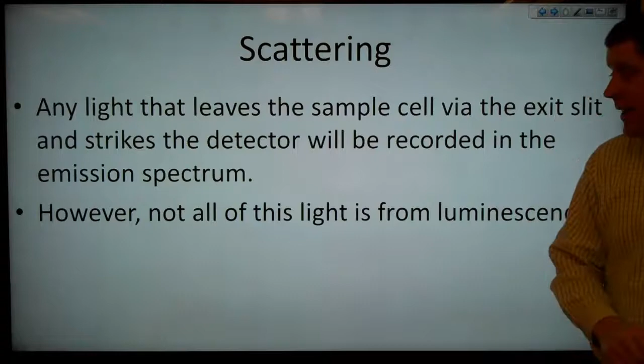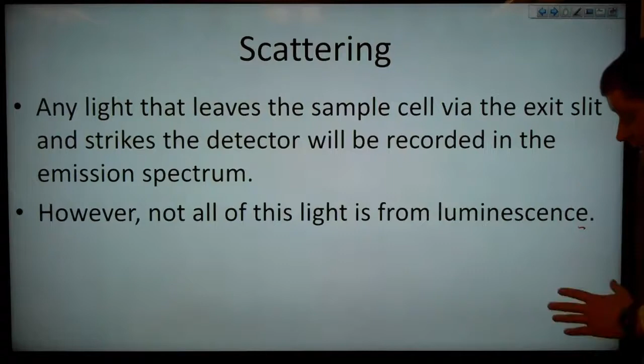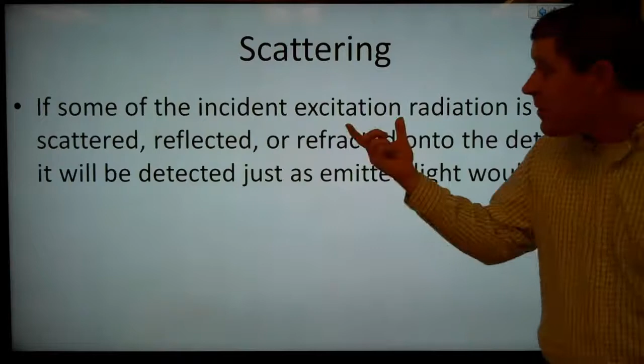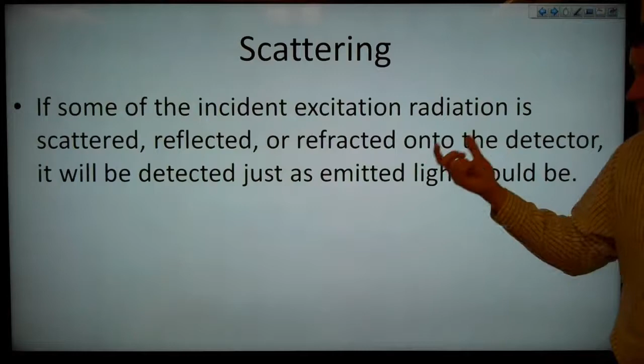So now let's talk about scattering. Any light that leaves the sample cell via the exit slit and strikes the detector will be recorded in the emission spectrum. But not all of this light is necessarily from luminescence, so it's not necessarily all really signal. If some of the incident excitation radiation is scattered, reflected, or refracted onto the detector, it will be detected just as any emitted light would.